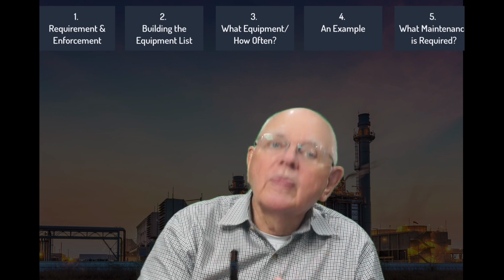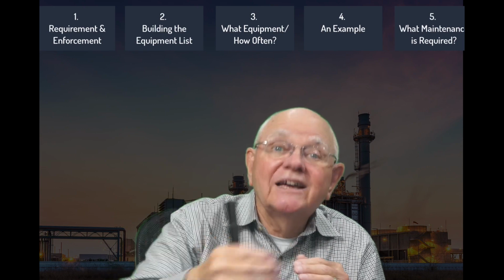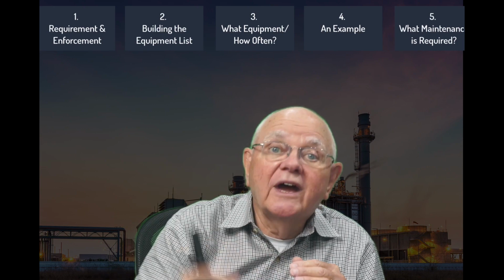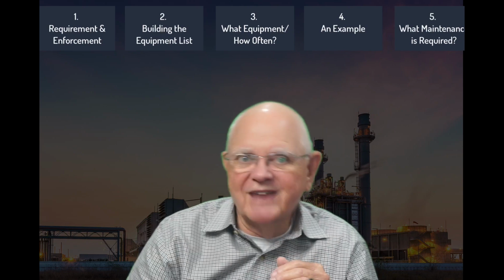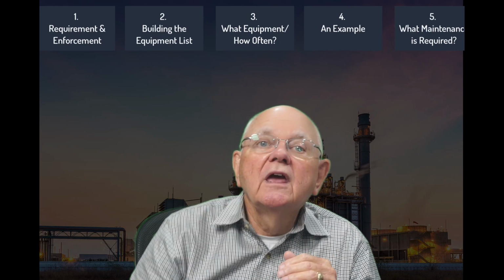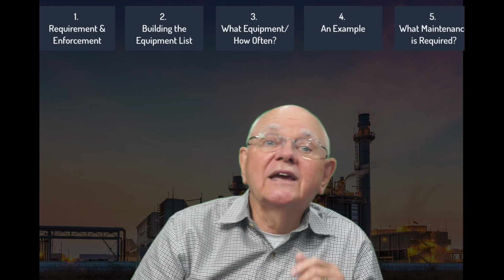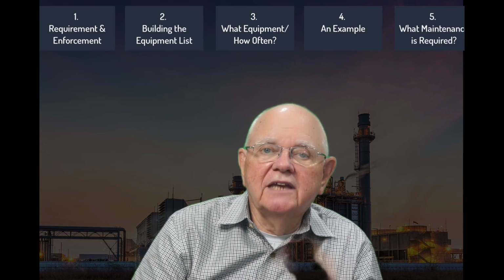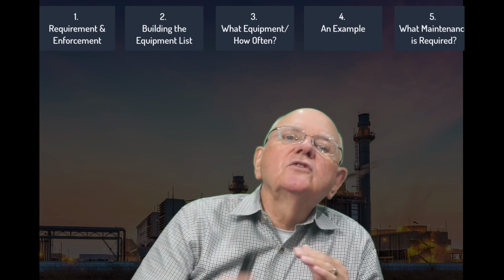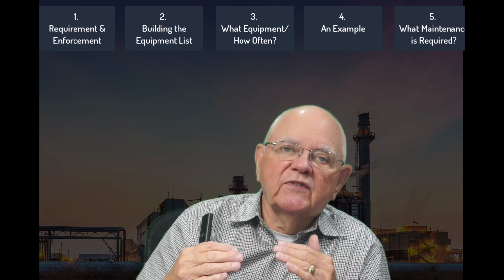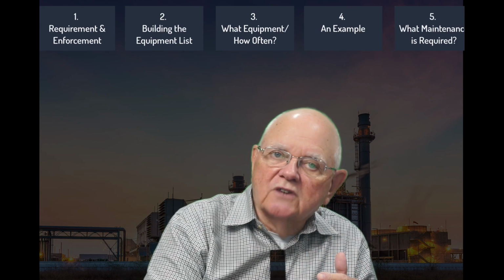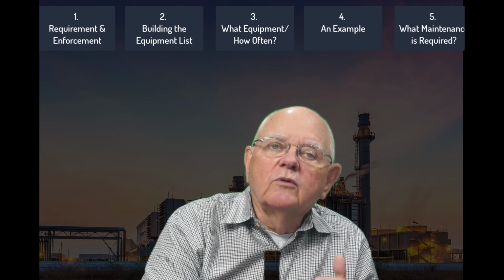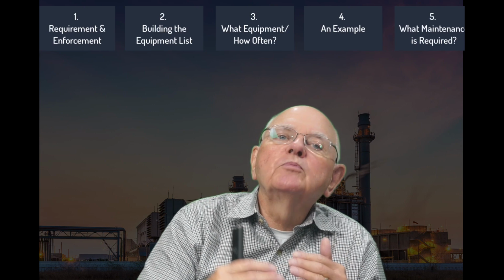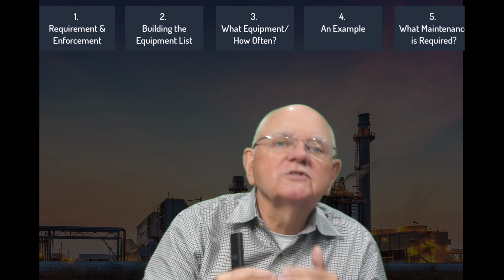I always want to do as-found and as-left tests - if I don't know that, I don't know what good my maintenance has been doing. And then I want to record all my inspection and test data. Once again, whether you're using 70B, maintenance test specifications, or manufacturer's instructions - which certainly has priority - whatever it is, you go out, perform that maintenance, and have a written procedure for it.